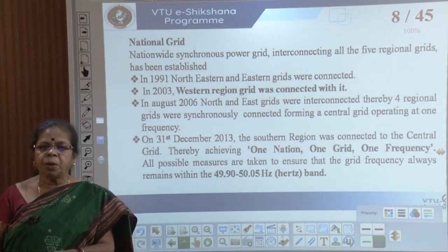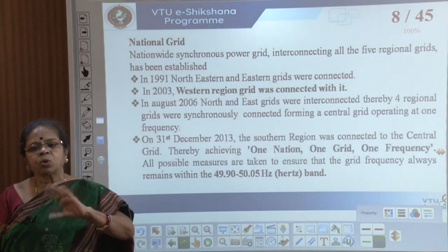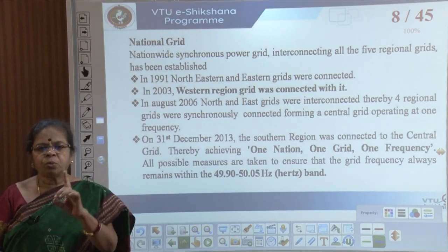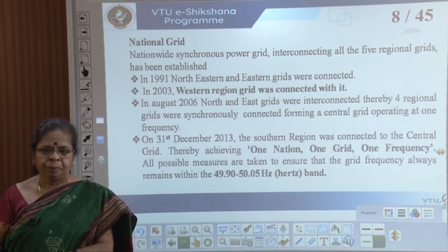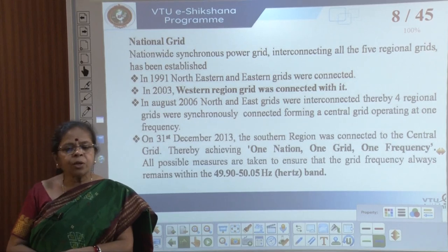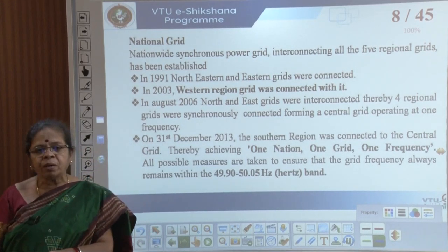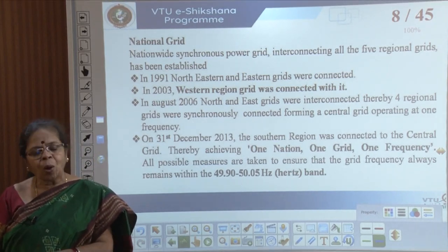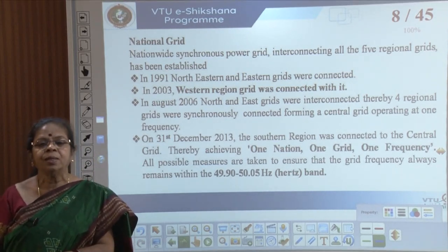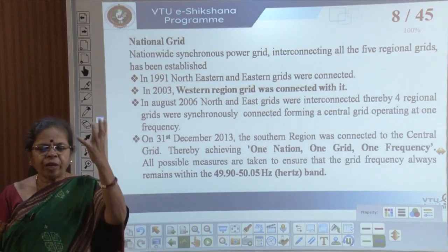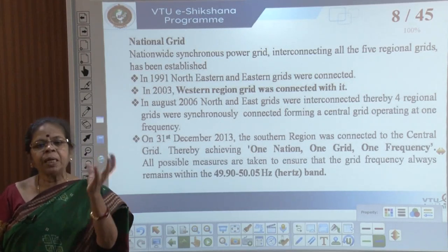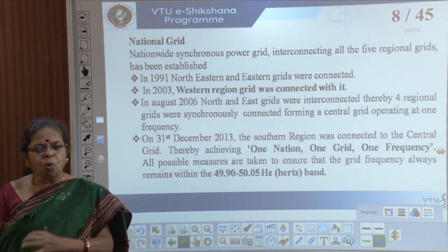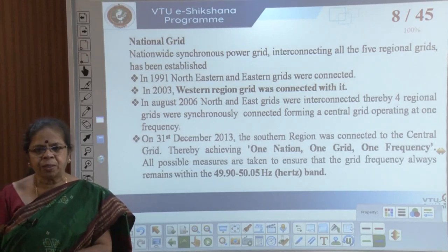Then on 31st December 2013, the southern grid was also connected to the central grid, and we now have one nation, one grid, one frequency. You may ask me, I told you that the Indian frequency is 50 hertz, so why am I saying one frequency specifically? It just means that though I specify 50 hertz, if the generation is more than the demand, that particular region would operate at a higher frequency. If the demand is more, it would operate at a lesser frequency.